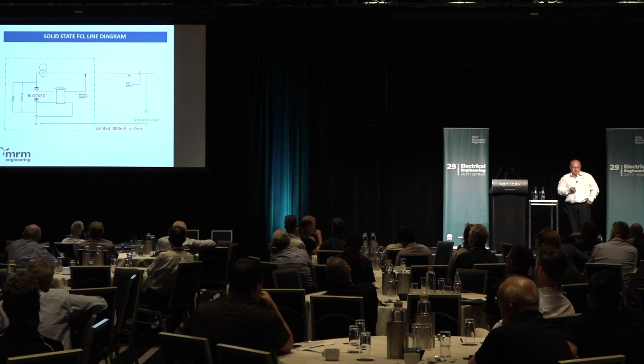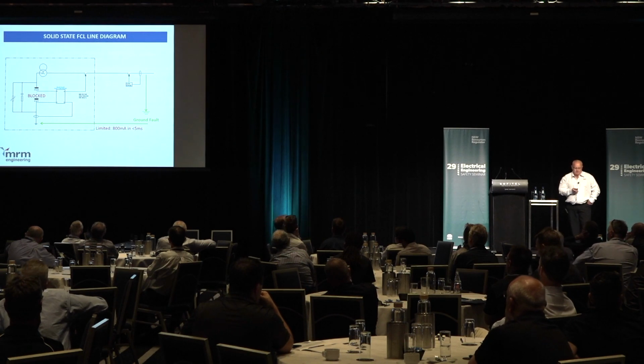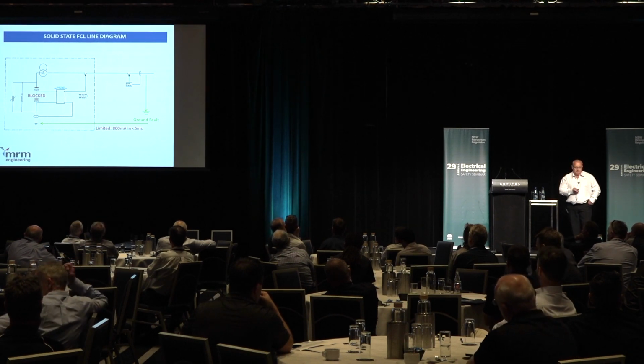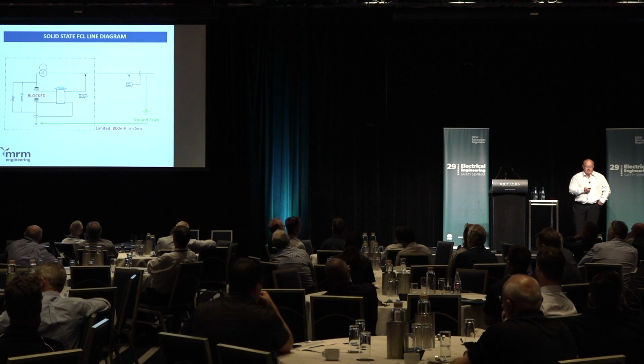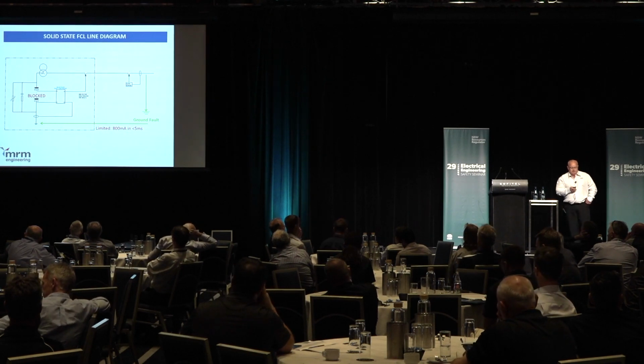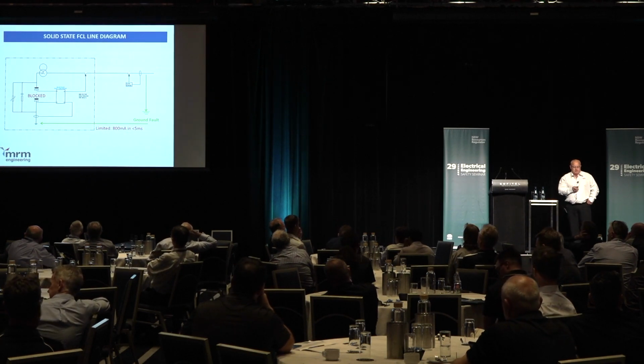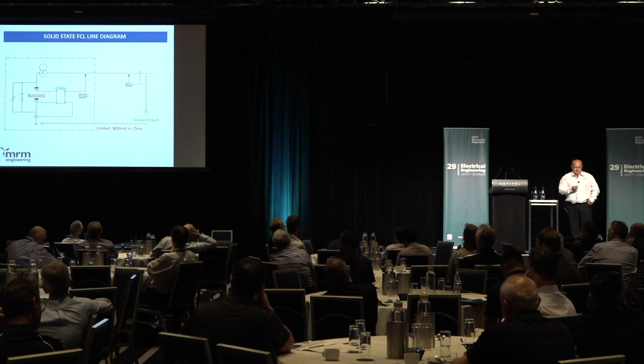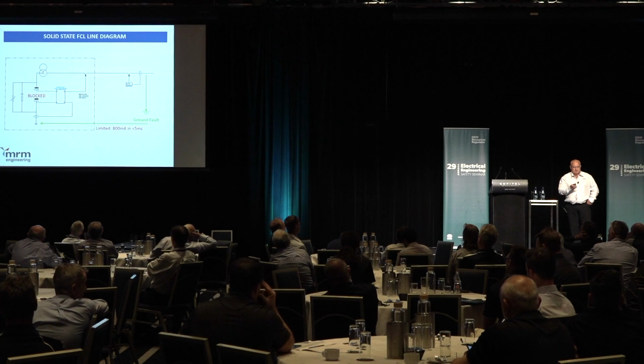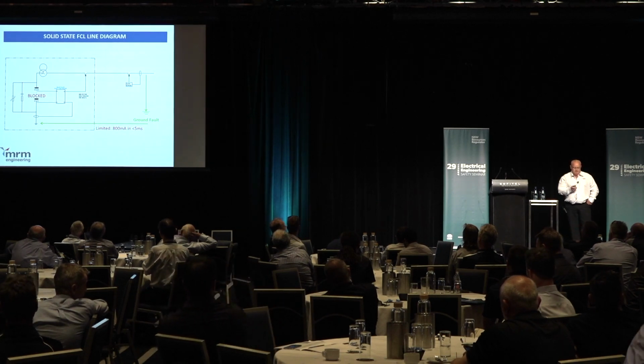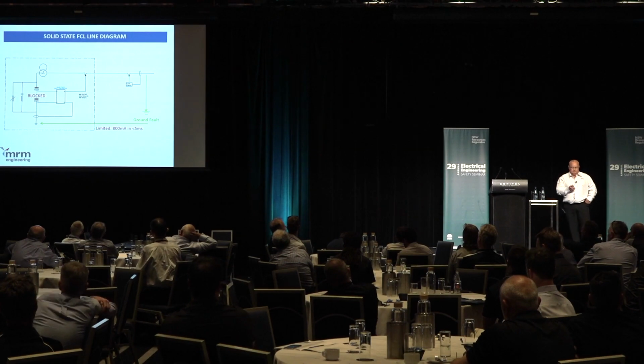So this is just a diagram of the solid state one, where the fault's out in the field, comes to the ground fault, returns back to the earth, and then the IGBT system shuts down and blocks any current flow. So they got limited to 800 milliamps in less than 5 milliseconds. So they're talking about very quick times now for clearance of faults and limited ignition.